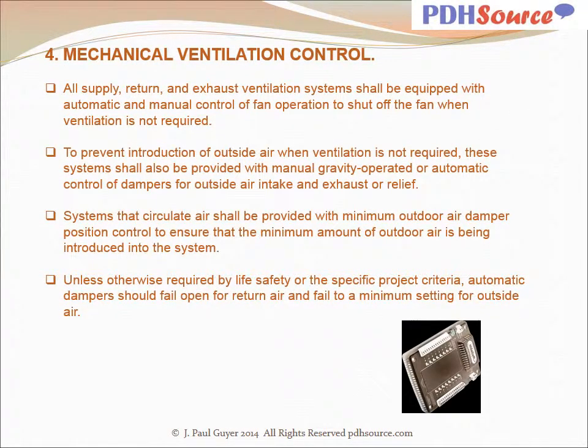All supply, return, and exhaust ventilation systems shall be equipped with an automatic and manual control of fan operation to shut off the fan when ventilation is not required. To prevent introduction of outside air when ventilation is not required, these systems shall also be provided with manual, gravity-operated, or automatic control dampers for outside air intake and exhaust or relief. Systems that circulate air shall be provided with minimum outdoor air damper position control to ensure that the minimum amount of outdoor air is being introduced into the system. Unless otherwise required by safety or the specific project criteria, automatic dampers shall fail open for return air and fail to a minimum setting for outside air.